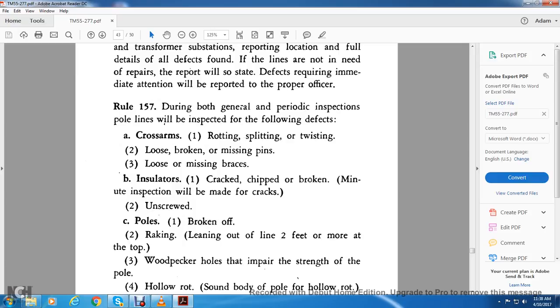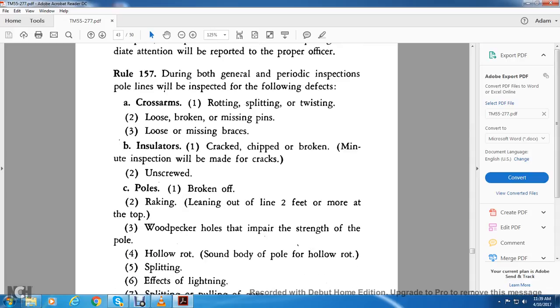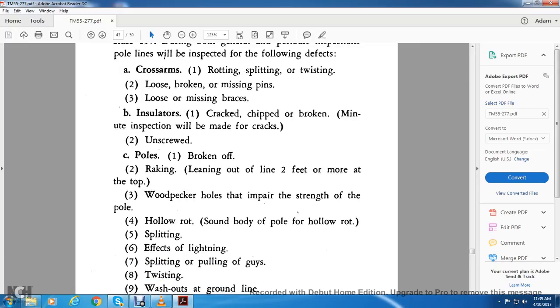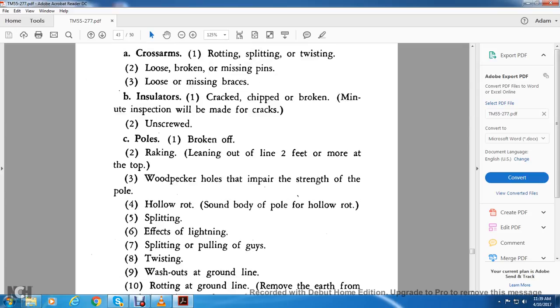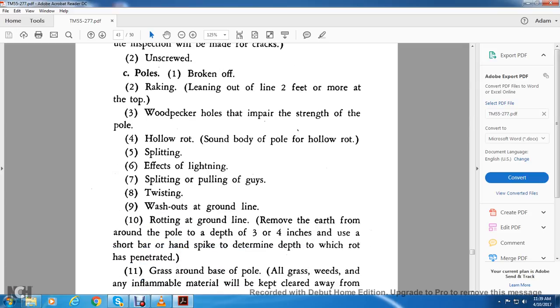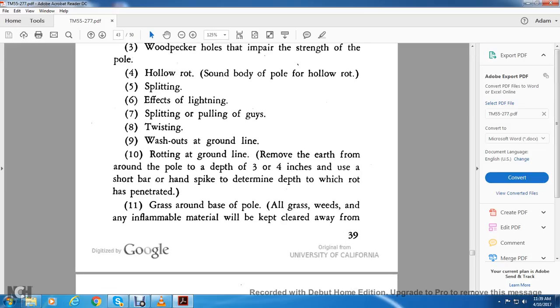Rule 157, during both general and periodic inspection, pole lines will be inspected for the following defects. A. Crossarms: rotting, splitting, or twisting, loosened, broken, missing pins, loose or missing braces, insulators cracked, chipped, or broken. Minute inspection will be made for cracks. Unscrewed. C. Poles: broken off, raking, leaning out of line two feet or more at the top, woodpecker holes that impair the strength of the pole, hollow rot, sound body of the pole, splitting, effects of lightning, pulling of the guys, twisting, washing out of the ground, rotting at the ground line. Remove the earth from around the pole to a depth of 3 to 4 inches, using short bar or hand spike to determine depth to which the rot has penetrated.